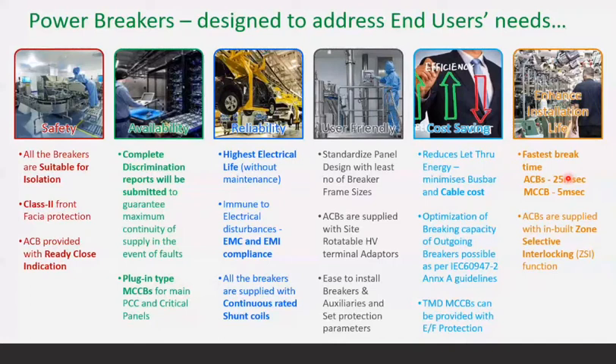As per the equation I square T, if my I at the time of fault is 50 kA, the square of this 50 kA multiplied by the time is itself a crore joule of energy. So how can we enhance our installation life? By minimum let-through energy, which reduces the stress on the installation.